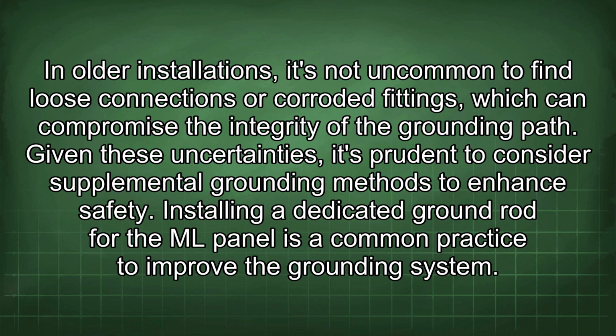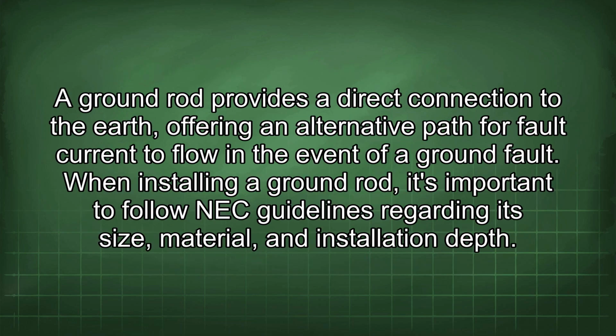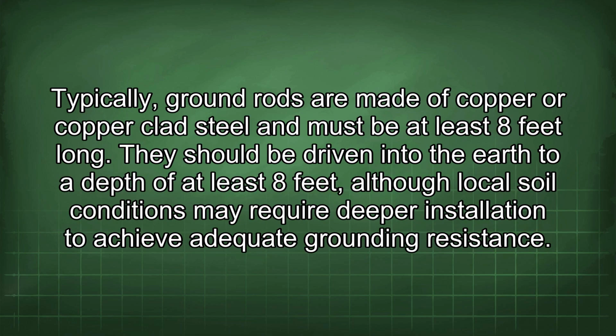Installing a dedicated ground rod for the ML panel is a common practice to improve the grounding system. A ground rod provides a direct connection to the earth, offering an alternative path for fault current to flow in the event of a ground fault. When installing a ground rod, it's important to follow NEC guidelines regarding its size, material, and installation depth. Typically, ground rods are made of copper or copper-clad steel and must be at least 8 feet long. They should be driven into the earth to a depth of at least 8 feet, although local soil conditions may require deeper installation to achieve adequate grounding resistance.